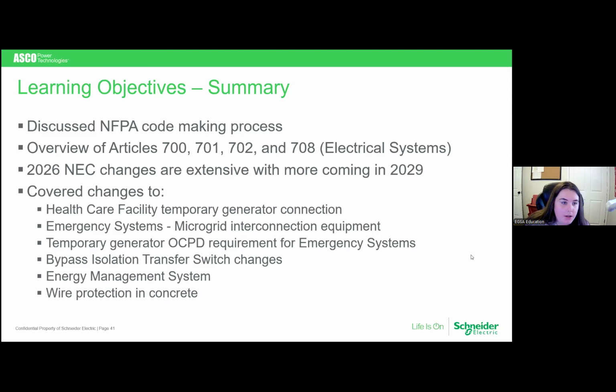Be sure to... oh wait, here's one more question. Sorry. The permanent generator is separately derived and the ATS is 4-pole, does the docking station slash MTS need to be 4-pole? How would the temp generator be grounded? Yeah, they should have a grounding rod at the location where that temporary generator would be hooked up, and yes, it would need to be 4-pole.